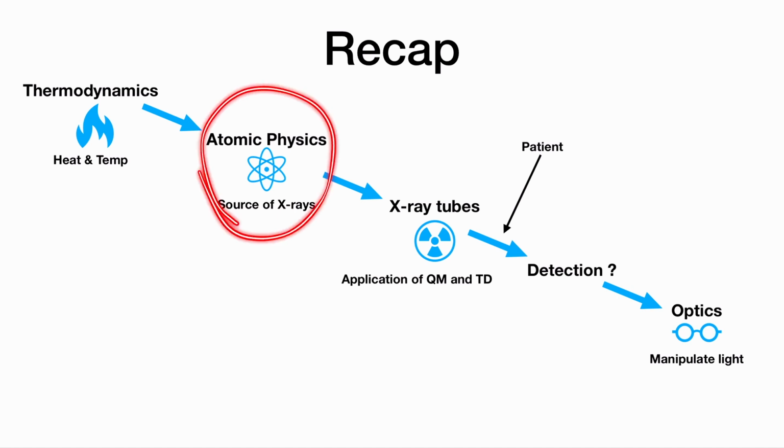This is how nature produces X-rays: when an atom is in an excited state, it emits a photon in order to assume a lower energy state. Nature prefers to be in a low energy state. High energy states are not stable in nature. Having learned these lessons, we therefore exploited nature, especially in its affinity for low energy states. We exploited it in order to produce X-rays at will. That's what X-ray tubes are.